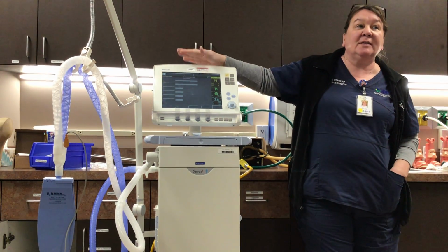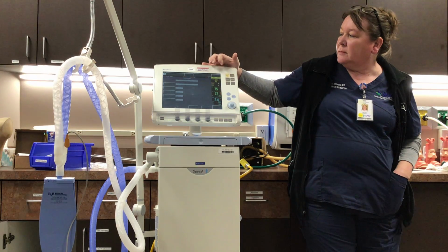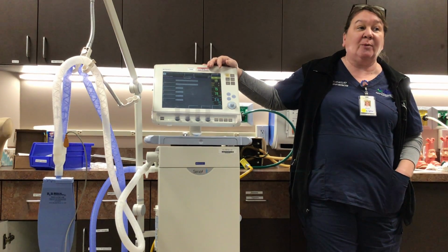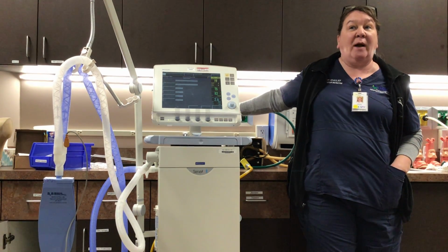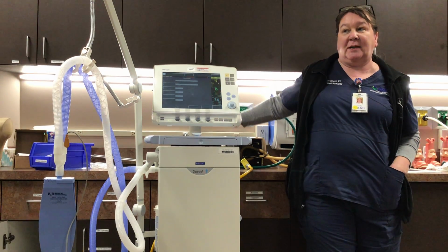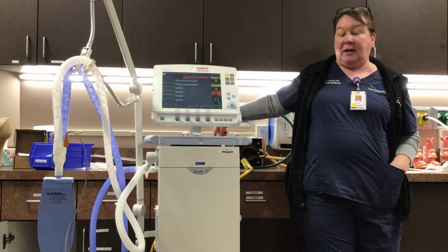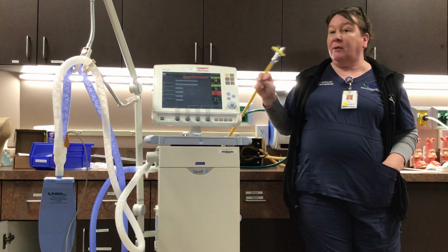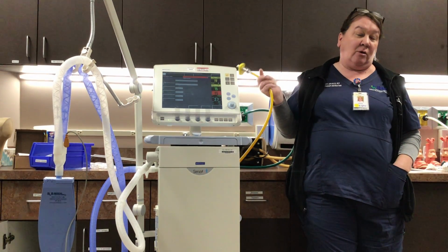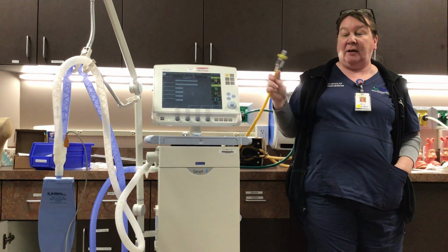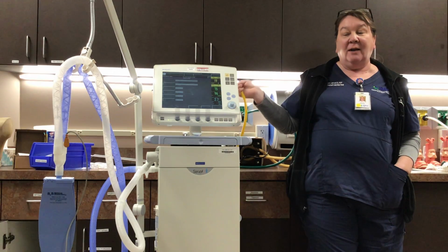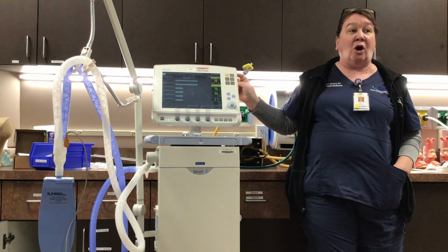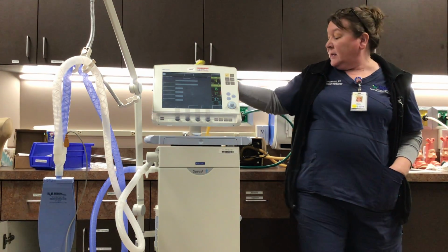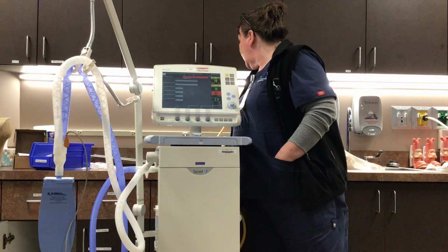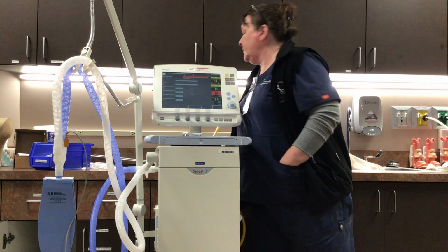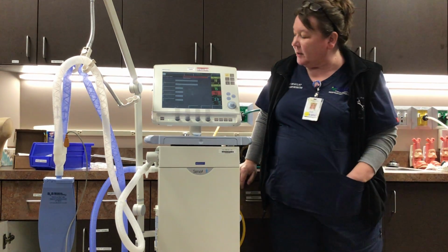So the ventilator is still working, and my patient is still getting breaths right now because I have at least one 50 PSI source hooked in. So a pneumatic and electric. It's just, it's gonna now not have its air source, so it's gonna go to 100%, and it's gonna alarm, it's gonna tell you, hey, something happened to your air source. These types of situations are rare, but they do happen. So I'm gonna hook it back in now, and it'll go back to the way it was. Let it go back down to where it's supposed to be.